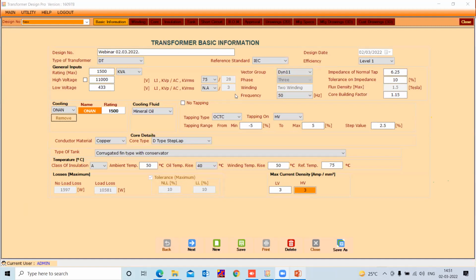Then you can go to the ratings alongside. You can see the lightning impulse levels: 75 kV is set for the HV winding, and you can go for 95 kV also. Similarly for the low voltage winding, 3 kV is the AC level. You have seen the vector group, Dyn11, and a frequency of 50 Hertz. It is for 3-phase, impedance at normal tap, tolerance on impedance, core building factor.